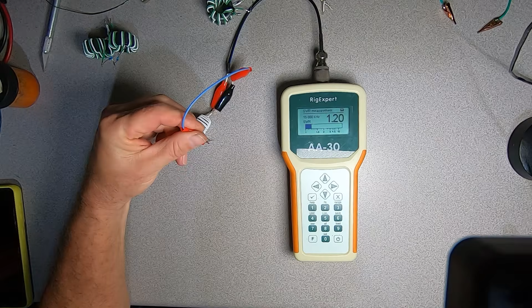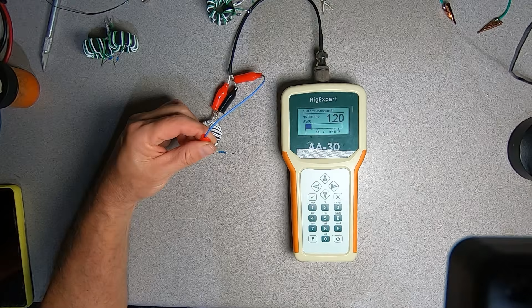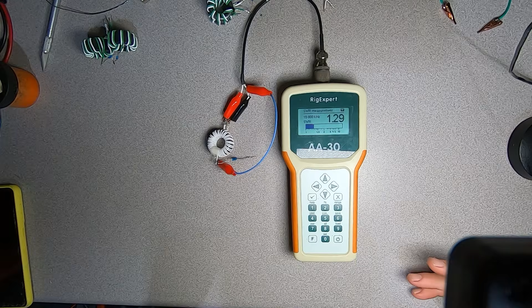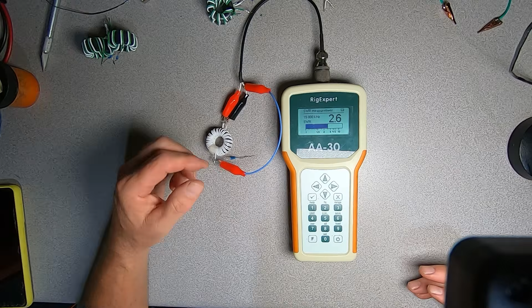Now let's show you something you don't want to see. So now we're going to repeat the test with this single core device. And we'll start here again in the middle. And you see we have a little bit of a change, not too bad. Move it over here, you can see we've got quite a bit of change on that leg. And now let's get one on here. And you can see there's not a whole heck of a lot of change, but that difference between this port and this port shows us that the transformer is not balanced.